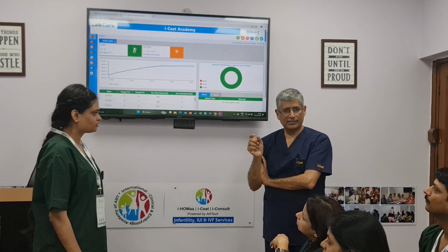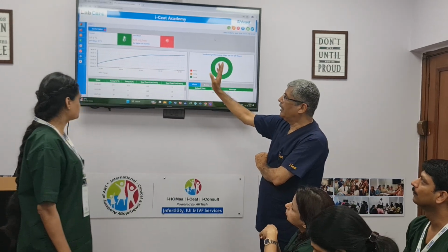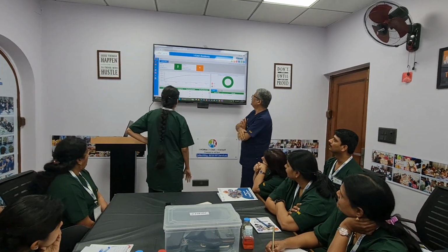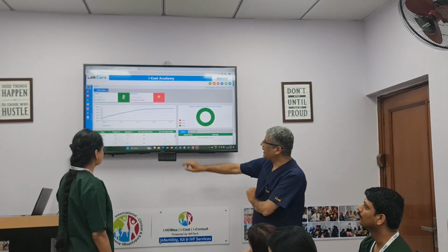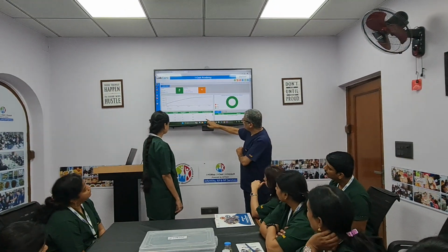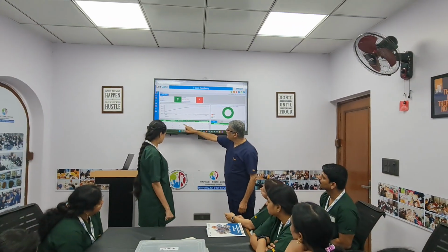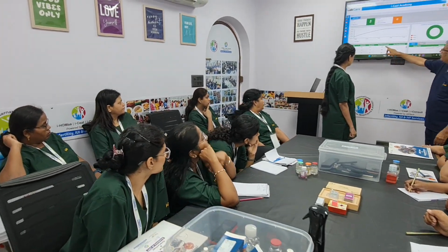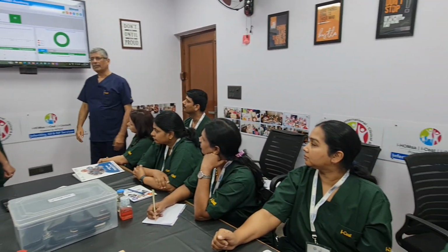How long did you open it? For 3 to 4 seconds. Sometimes it will come to normal. And that's a graph which you always have. It will tell you the time. So your gas flow keeps coming here. This is the gas flow chamber. There are two chambers, one and two. Two is maintaining at 17 ml per minute. And temperature didn't change at all after you opened the incubator. And the gas flow in one is 670. Sometimes it will come to 17, 18. Any questions from me?